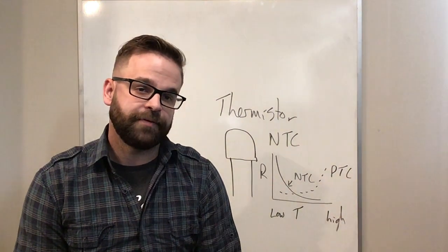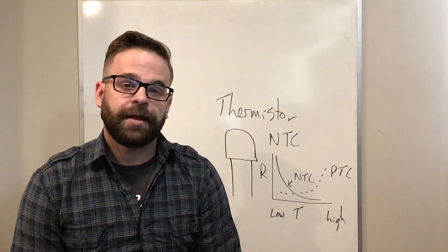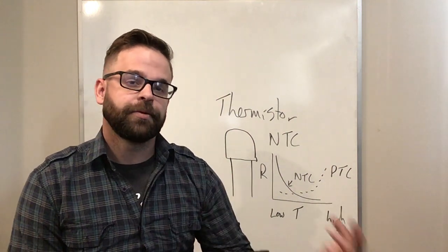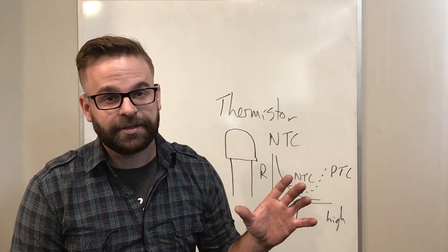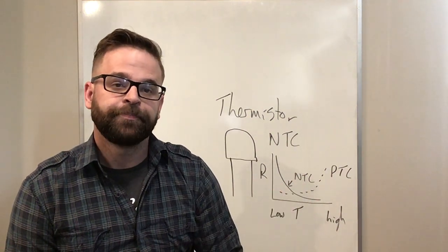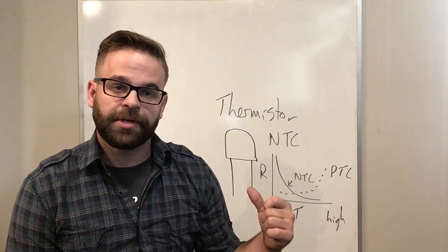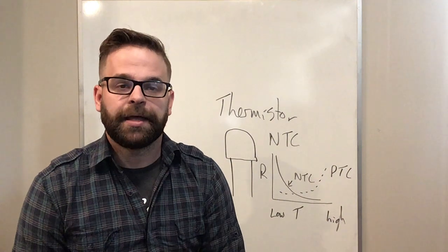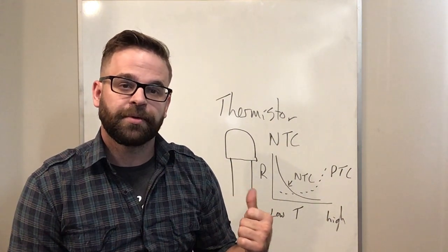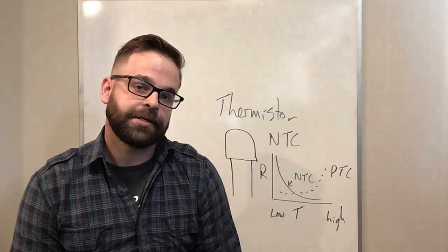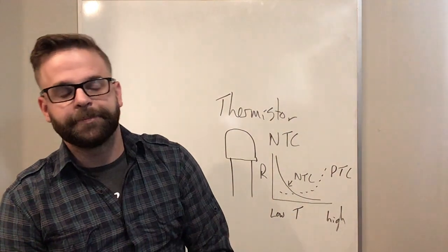So a lot of times you need 5, possibly 6, sometimes even 7 wires. So rather than having to run new wire through your house to accommodate the new thermostat, the thermostat can just stay right by the furnace, and I run a little remote sensor, a thermistor, upstairs, and it only needs 2 wires because there's only 2 terminals on them, and so I can do the exact same thing without having to add all that extra work.